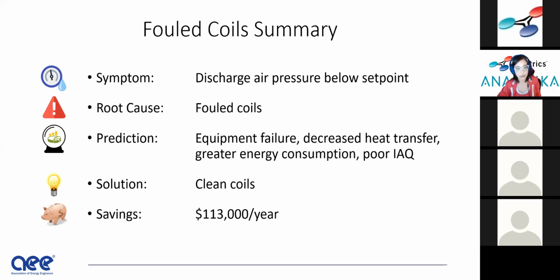Equipment failure, I talked about some of what we're predicting, what could possibly happen there, the consequences. An easy, well, I say easy, straightforward solution to clean them. You can do this power wash, or I've heard of UVC and things like that. There's a variety of ways to clean coils. That's not my expertise. Savings was $113,000 a year for fouled coils. And that's not thinking of the indoor air quality issues. I'm always shocked as a mechanical engineer, it makes sense, right? A dirty coil, you're not going to get as much heat transfer, but wow.